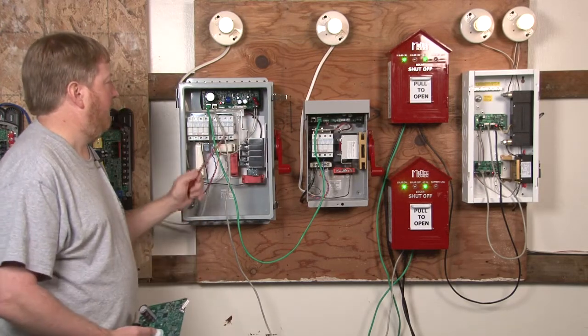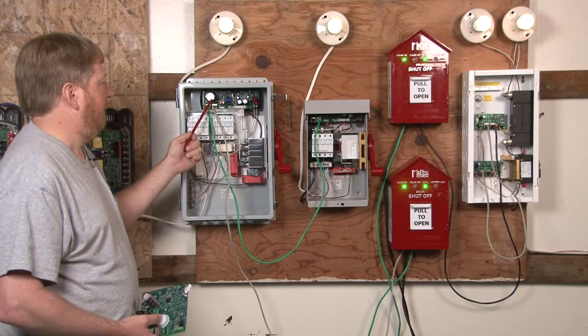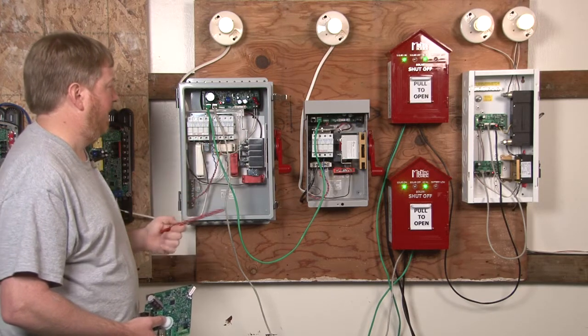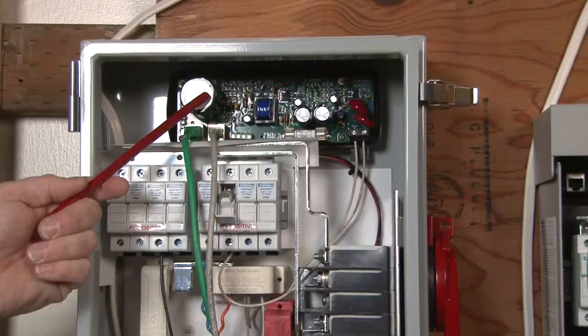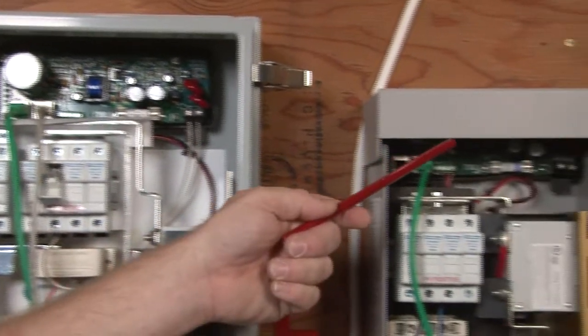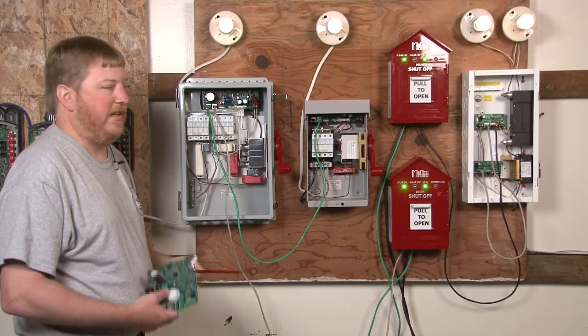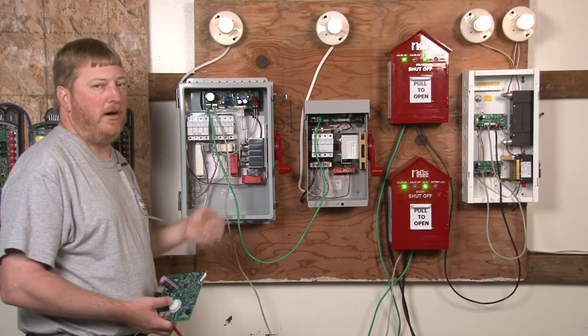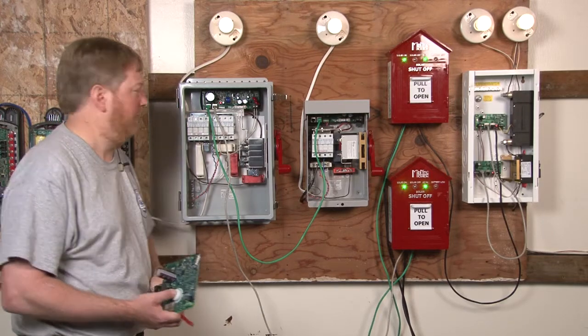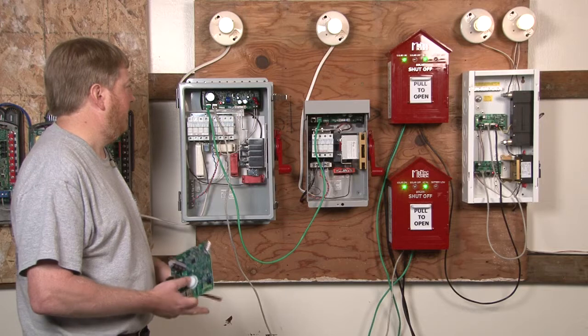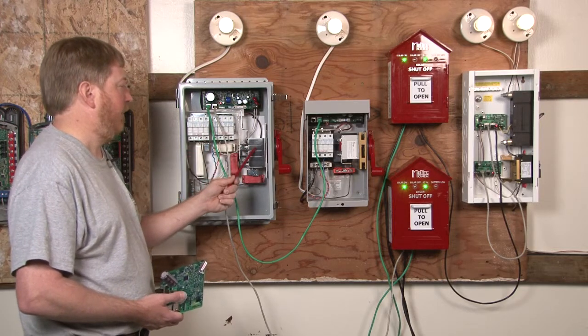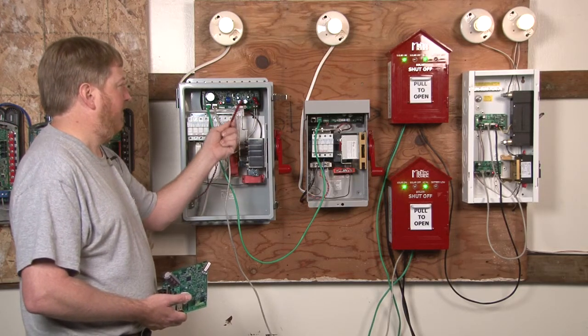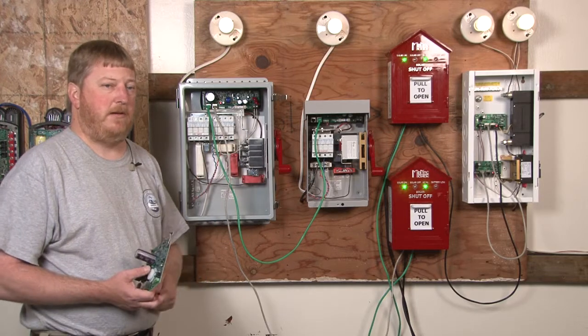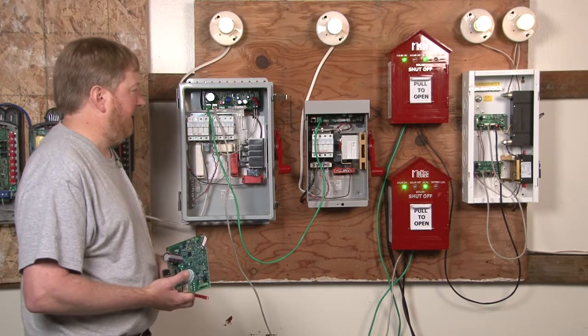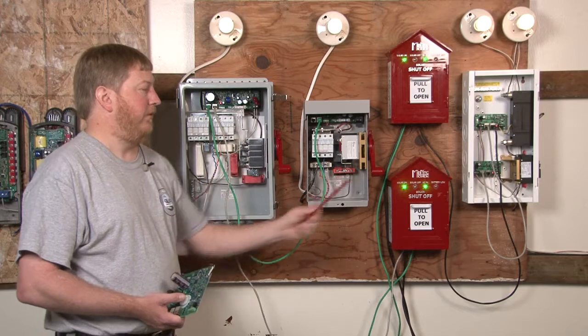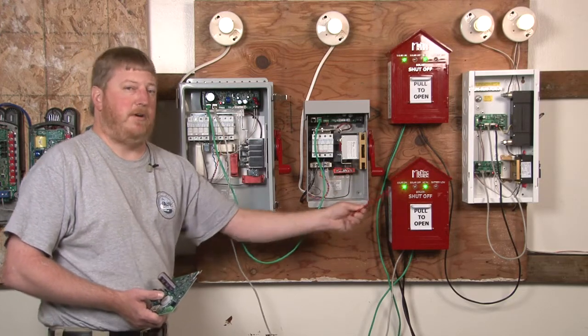The first thing I want to talk about is the combiner boxes, the power supply boards, the switches, etc. As you'll see, each one of these combiner boxes has a power supply board in it. This is an add-on that you put in the combiner box, or we can put it in if it's purchased that way. What that does is it stores energy to turn off the switch. It also has a power supply in it that's powered off the PV array to charge that capacitor up to flip the switch, and also keep the rechargeable batteries in the birdhouse charged.